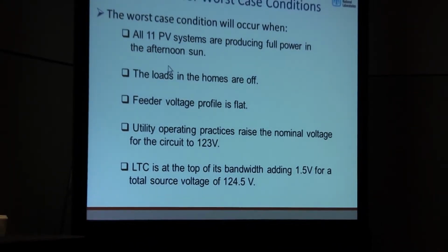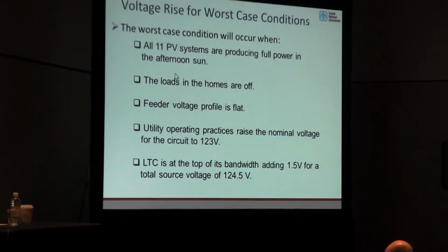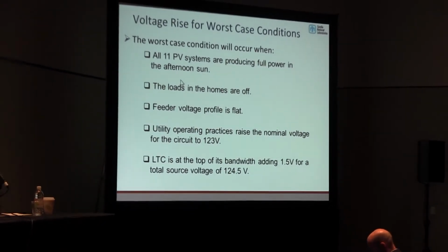So we had to make a lot of assumptions before we put this modified screen together, because you're looking for a worst case scenario. So here are the worst case scenario assumptions we made. One, all 11 PV systems, i.e. one on each house, are all producing maximum power in afternoon sun. We assume that nobody's home at the houses, so it's going to make it for the worst case condition. All the loads are off. We're going to assume the voltage profile is flat.